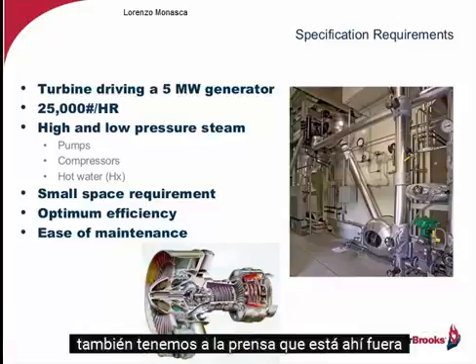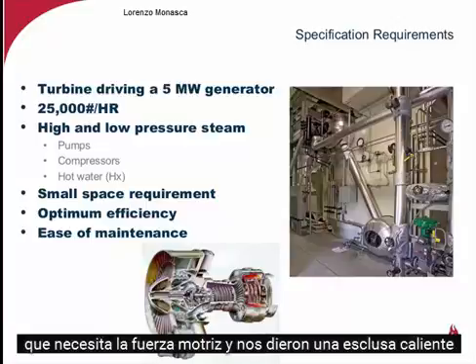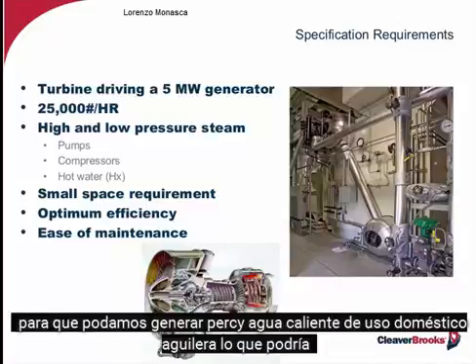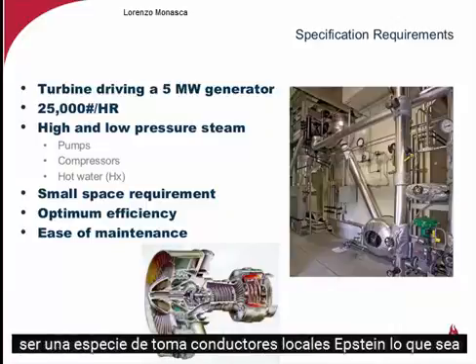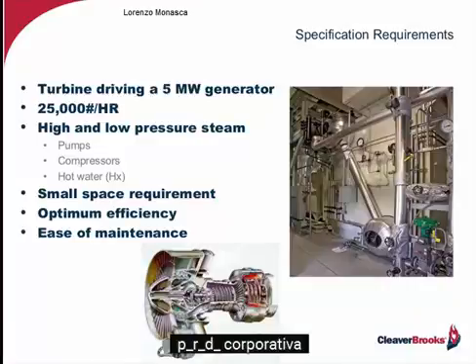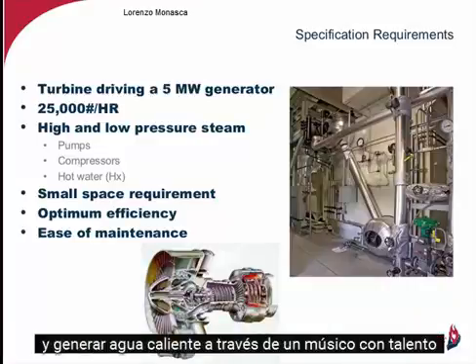We also have compressors out there that need some motive force, and we've got a hot water need, so we can generate hot water for CIP or domestic use, whatever it might be. So we're going to take that steam, low pressure, high pressure, whatever it is, go through a PRV, and generate hot water through a shell and tube heat exchanger.